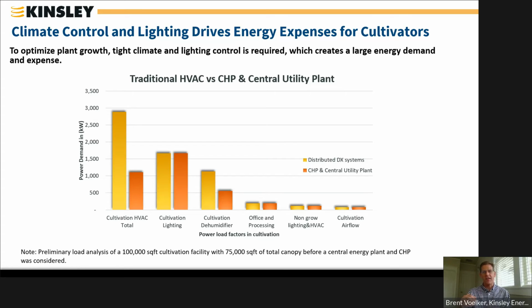This is what we call the spark spread, where you stack three elements of operation, the cost of capital, the cost of fuel, plus the cost of service, giving you the total cost of generating a kilowatt hour from the CHP. You compare that to the cost of utility power, and when there's a delta there, you've got a spark spread that pays you back, pays for the CHP system.